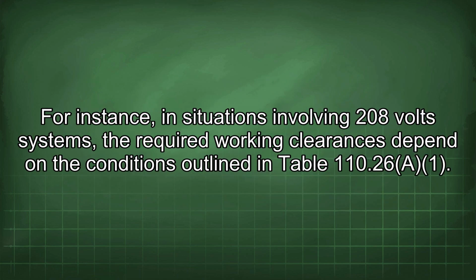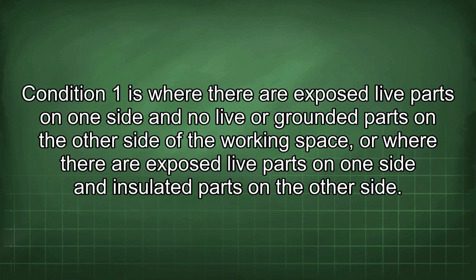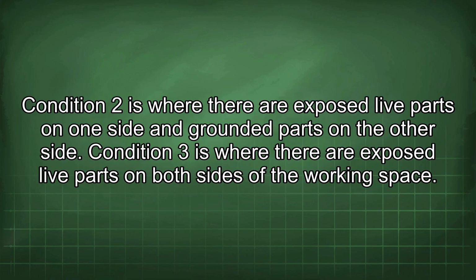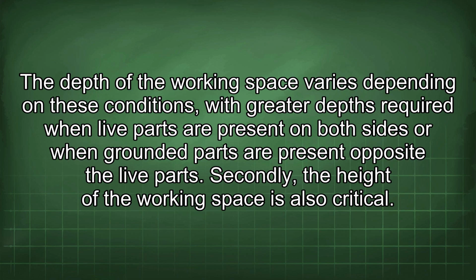For instance, in situations involving 208-volt systems, the required working clearances depend on the conditions outlined in Table 110.26(A). Condition 1 is where there are exposed live parts on one side and no live or grounded parts on the other side of the working space, or where there are exposed live parts on one side and insulated parts on the other side. Condition 2 is where there are exposed live parts on one side and grounded parts on the other side. Condition 3 is where there are exposed live parts on both sides of the working space. The depth of the working space varies depending on these conditions, with greater depths required when live parts are present on both sides or when grounded parts are present opposite the live parts.